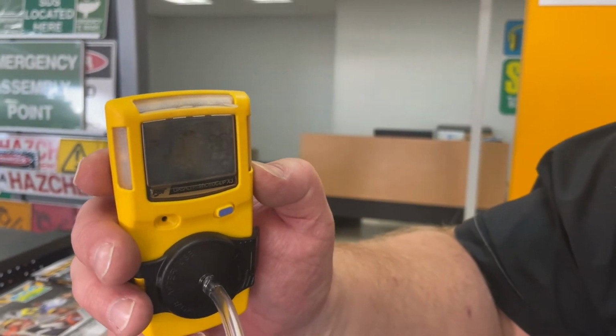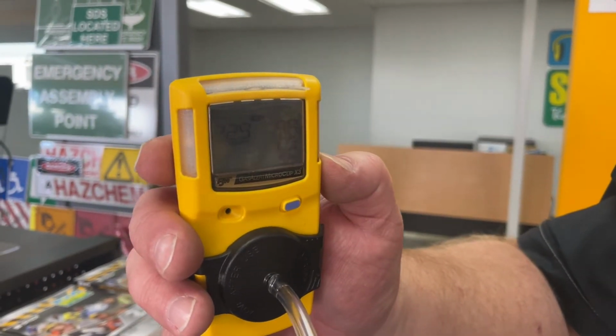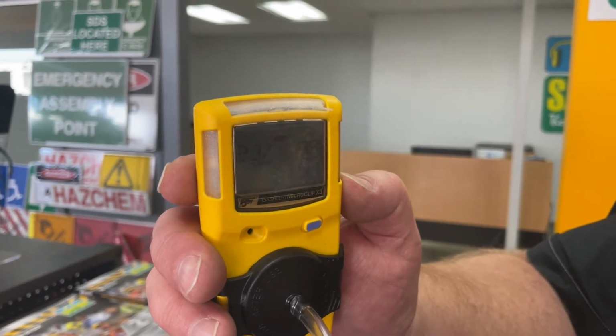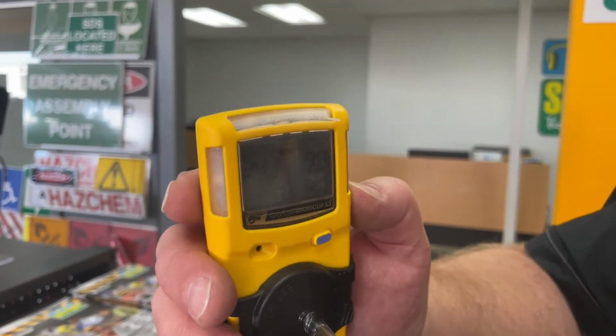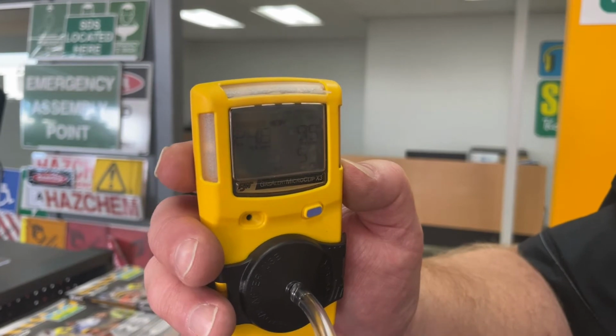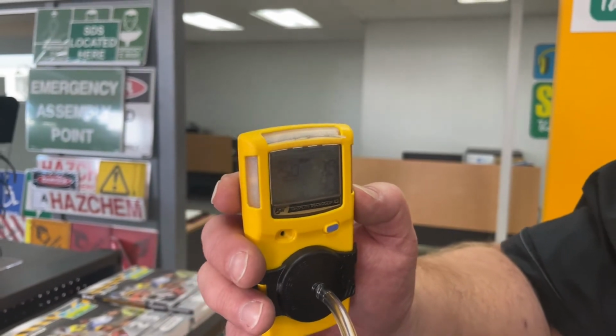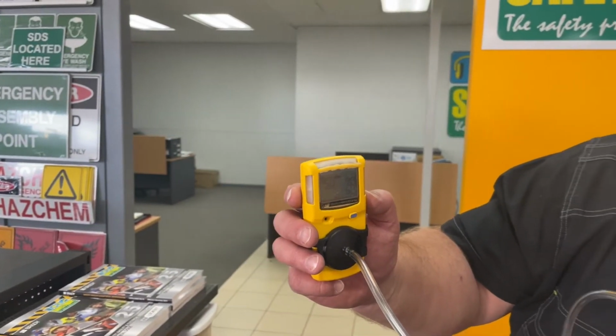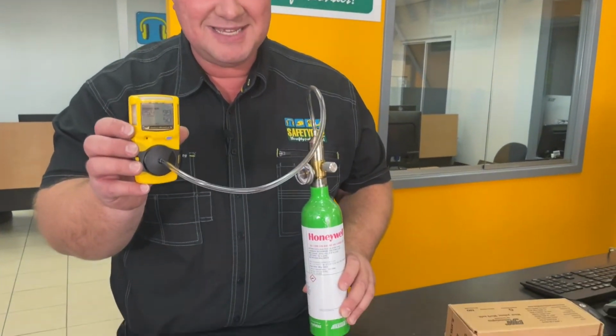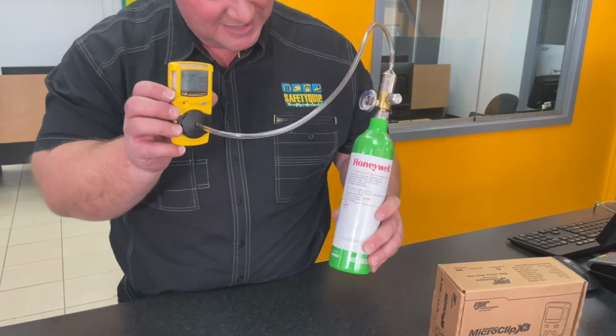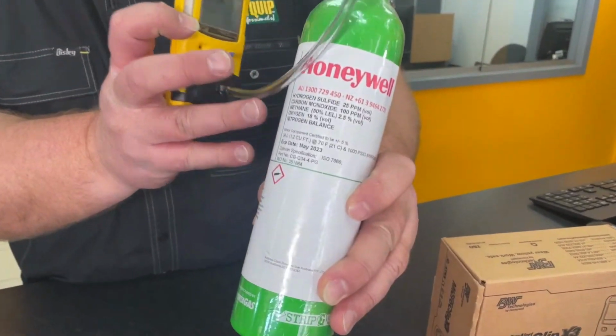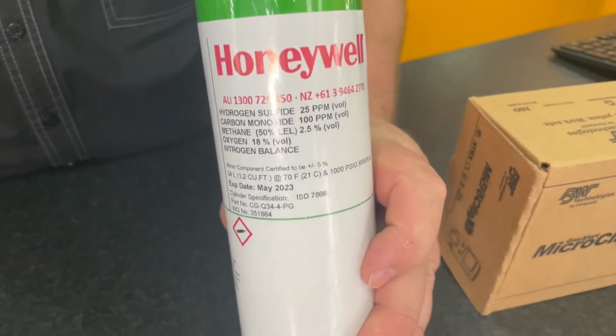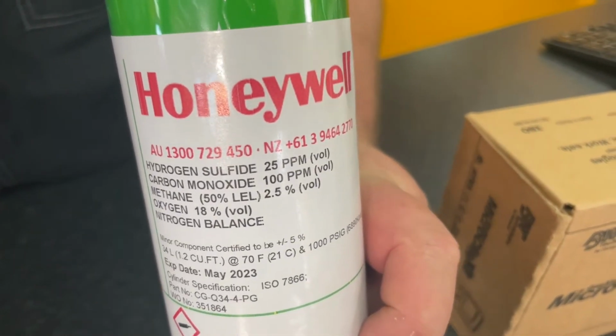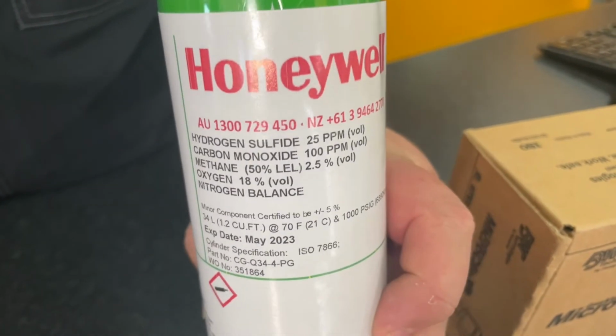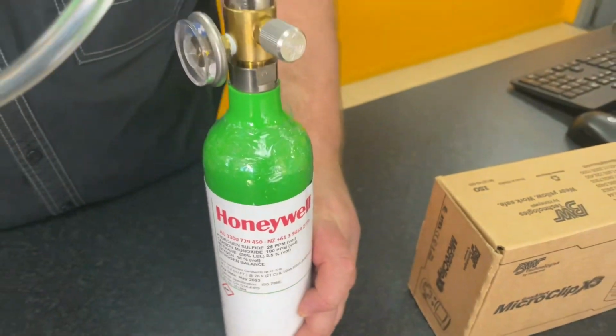So that'll need to run for a little while until it identifies the gas properly and stabilises at an appropriate level. Now, whilst that's doing that, it's important to talk about the gas cylinder that you have needs to have the correct mix of gas that the gas detector understands you're using to do the calibration. So you can see on the label there's a percentage or a ppm for each of those 4 gases. This is the genuine Honeywell gas for this particular unit.